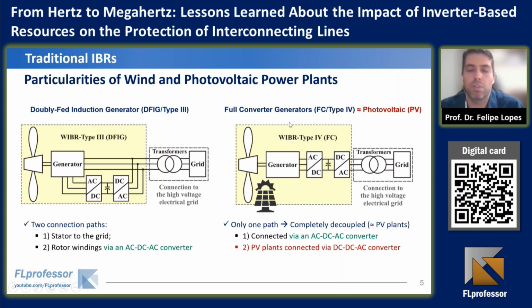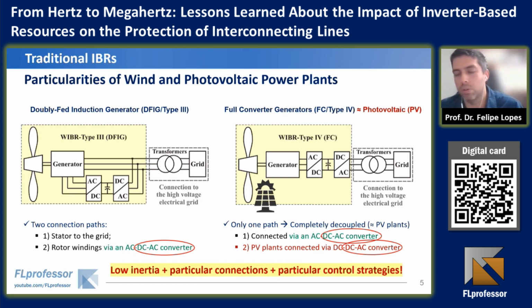And in this case, the full converter is completely decoupled from the grid, since it has only one path of connection. It is very similar to the photovoltaic topology, but the difference is that the first converter here is not an AC-DC, but rather, when we consider the PV plants, we have DC-DC-AC converter. But in our case, if you see the second stage of these converters, we have a DC to AC converter, which are the inverters. And the question here is how these inverters are controlled and how they can affect protection functions or even fault location functions.